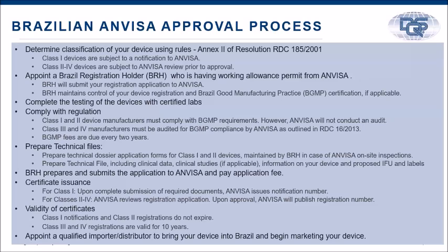In order to incorporate the requirements of Brazilian ANVISA, those regulations are under the MDSAP program now. So you can use MDSAP to demonstrate compliance to those requirements from a quality system perspective. Mainly, for all these five geographies, the question is how you integrate those requirements into your quality system.